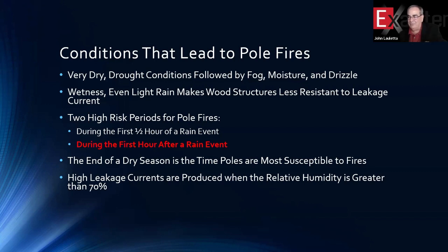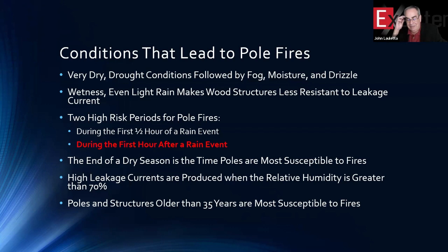And then high leakage currents are produced during high humidity, where the humidity is greater than 70%. So if you live in an area with high humidity, you're going to have more associated pole fires than places that are very dry. The other thing that is very important to understand is that as the poles themselves dry out, they become more apt to participate in a fire. And it seems to be something on the order of 35 years or older when poles really begin to contribute to the pole fire problem itself.